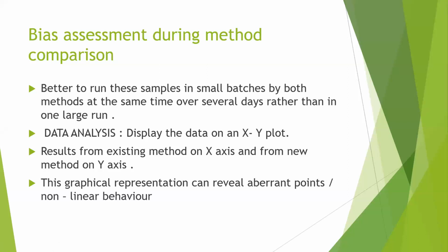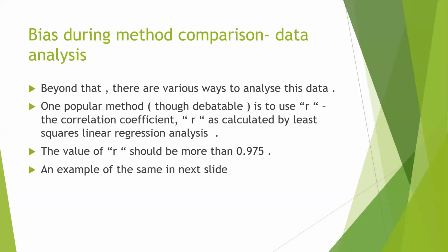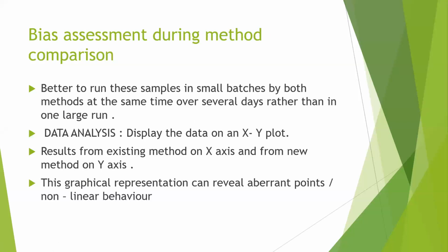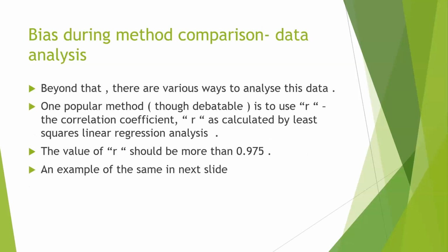You display the data on an XY axis plot, with results from the existing method on the X axis and from the new method on the Y axis. This graphical representation will show you the correlation between the two methods, the new method and the older method. Beyond this basic look at the data to see if it's linear or has any aberrations, there are many ways to compare methods.